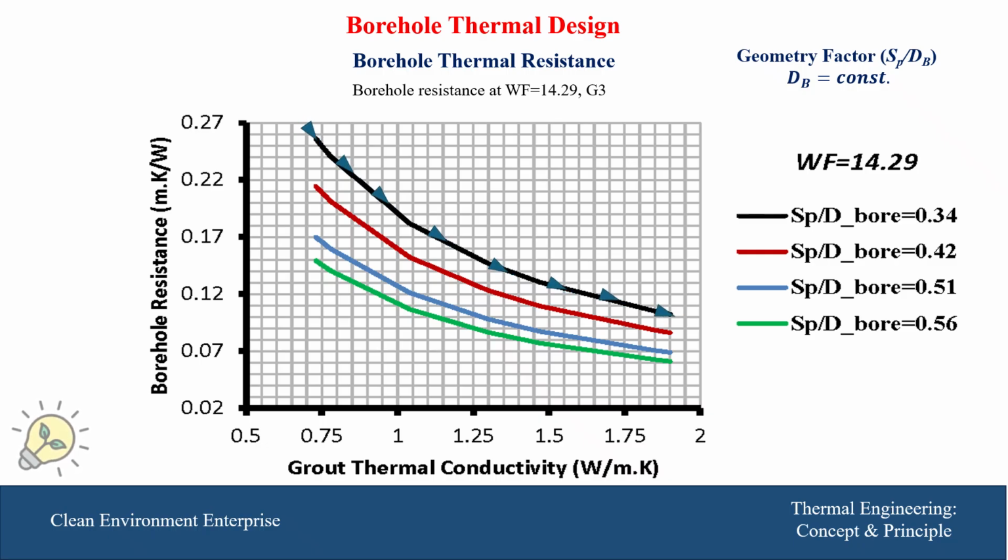And as we increase the geometry factor from 0.34 to 0.56, the thermal resistance is reduced by a tremendous value, and of course that will be reflected on the heat loading of the heat exchanger and the thermal performance of the heat pump itself.